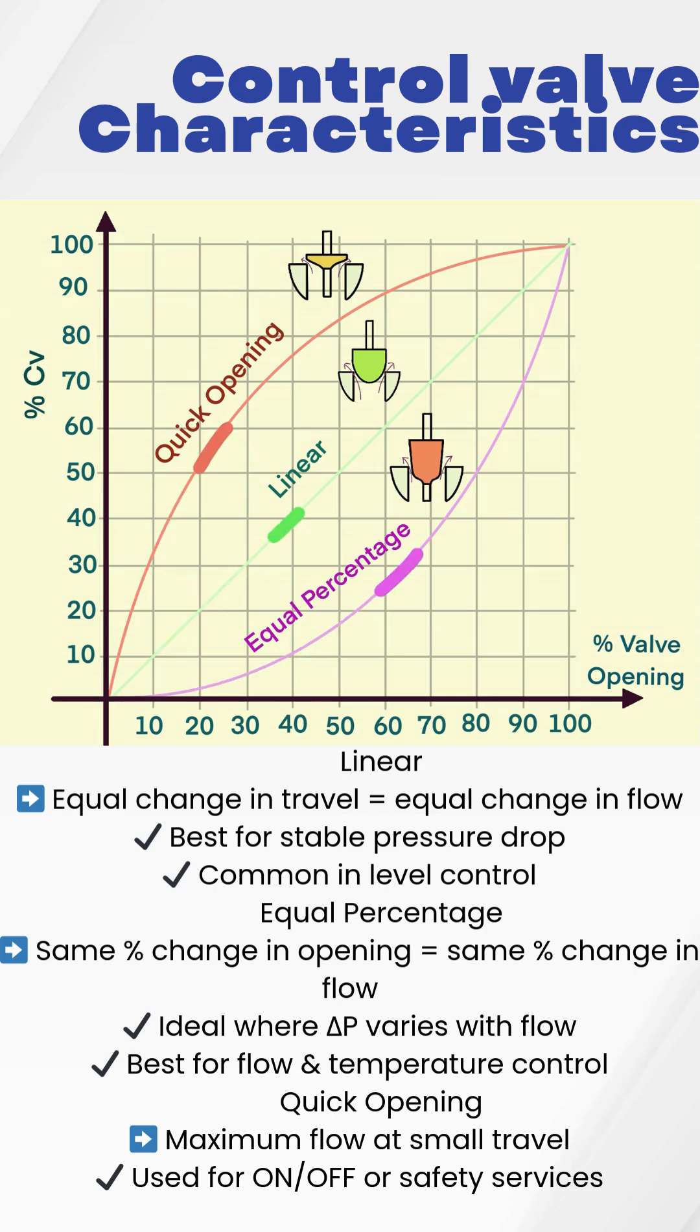So how do you choose? If your process has wide flow variation and changing pressure, go for equal percentage.